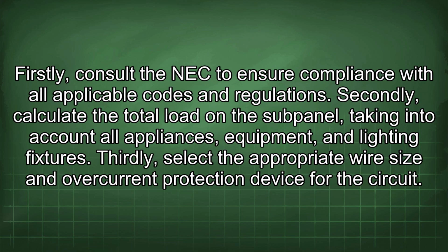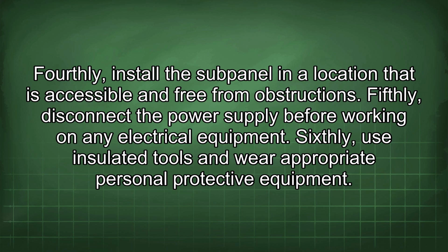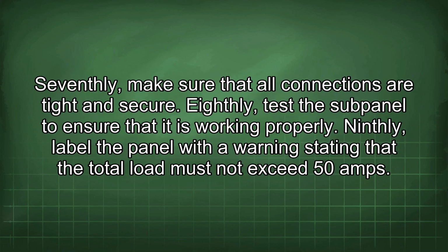Firstly, consult the NEC to ensure compliance with all applicable codes and regulations. Secondly, calculate the total load on the subpanel, taking into account all appliances, equipment, and lighting fixtures. Thirdly, select the appropriate wire size and overcurrent protection device for the circuit. Fourthly, install the subpanel in a location that is accessible and free from obstructions. Fifthly, disconnect the power supply before working on any electrical equipment. Sixthly, use insulated tools and wear appropriate personal protective equipment. Seventhly, make sure that all connections are tight and secure.